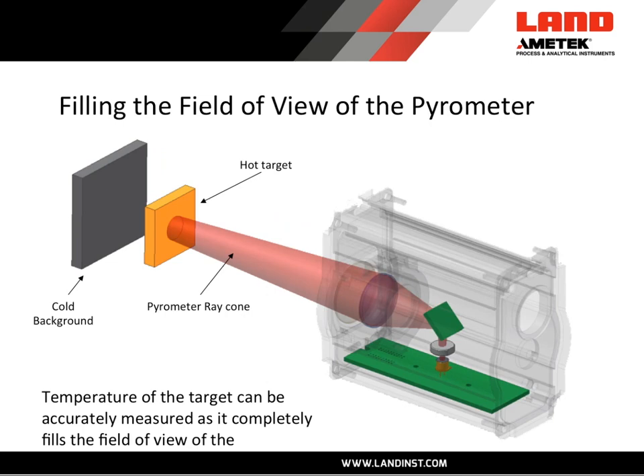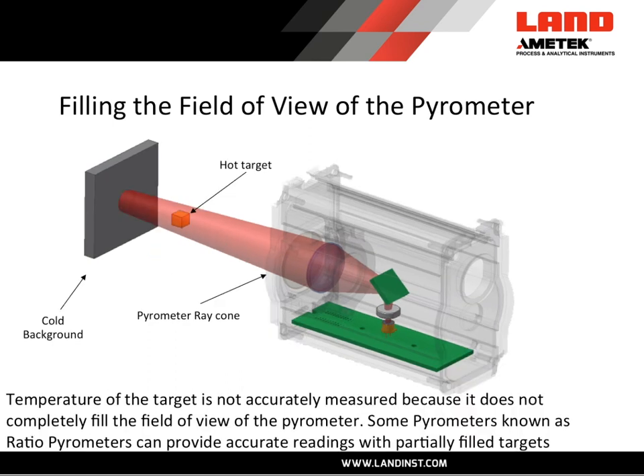In this schematic you can see the same pyrometer looking at a hot target. With a conventional monochromatic pyrometer the temperature reading comes from averaging the temperature of everything in that target spot, so you want the hot target to be larger than the target spot so it's not also averaging background temperature. If the hot target does not fill the field of view of the pyrometer, it will average lower temperature from the cold background and give you a falsely low reading. Always ensure the instrument is focused onto the object and is capable of seeing the object with none of the background.